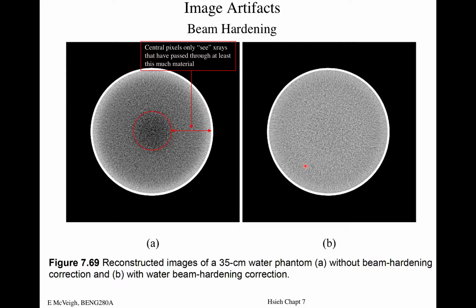This gets really challenging when, say, there's a piece of metal right here, right? And then that gives you a huge shadow behind it, such that all of the projections that hit the metal essentially occlude your vision of anything back here. And so there's just missing data. And so to do that, you have to do an iterative process to find out where the occluder is. Behind it, I now know that these views should just not be considered when I'm trying to figure out what the Hounsfield unit is.